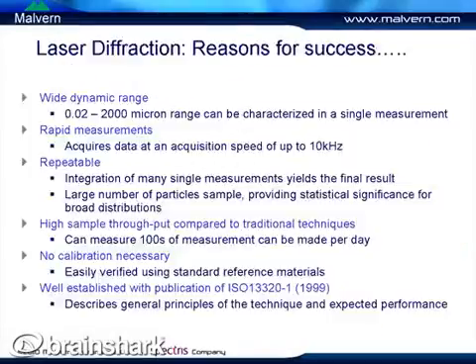Laser diffraction has been a successful particle sizing technique for a long time, more than 30 years now, and that's due to a range of different reasons. Looking at the wide dynamic range of the instrument, you can measure particles from 20 nanometers up to 2 millimeters in a single measurement without having to change any lenses.